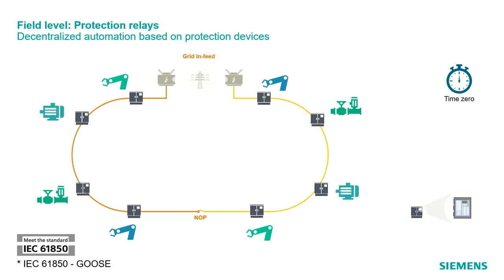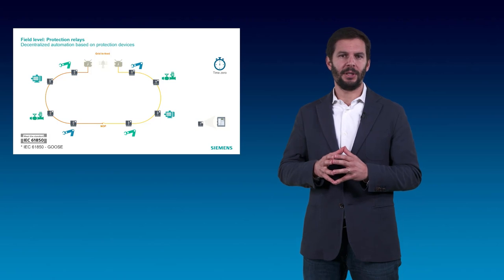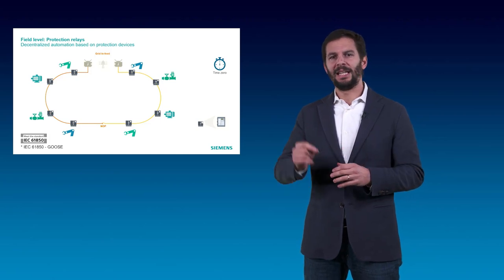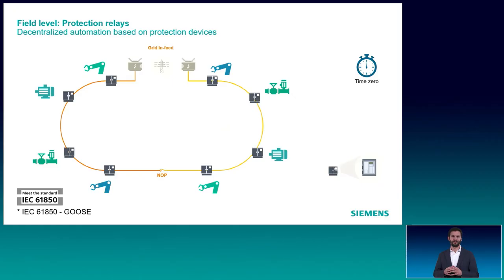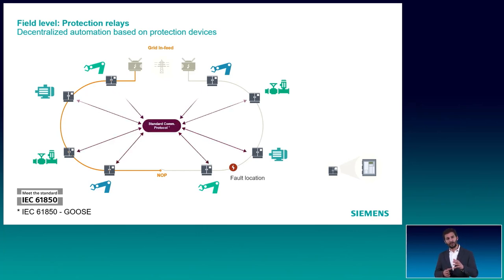Finally, we have also mentioned the possibility to deploy intelligent automation on the field level. With the most advanced IEDs, Siemens protection devices currently offer fully decentralized architectures for critical operations — especially relevant in scenarios where critical loads are supplied by different medium-voltage and low-voltage stations. Interconnected in a ring structure to the primary in-feed station, the so-called self-healing application can minimize the impact of power outages on those loop structures. Once a fault occurs, the intelligent devices will immediately locate it, supported by the multicast of IEC 61850 GOOSE messages. Once located, the devices will immediately operate the breakers to isolate the faulty section, restoring power to the remaining areas of the plant without any human or SCADA intervention — all done in a blink of an eye.